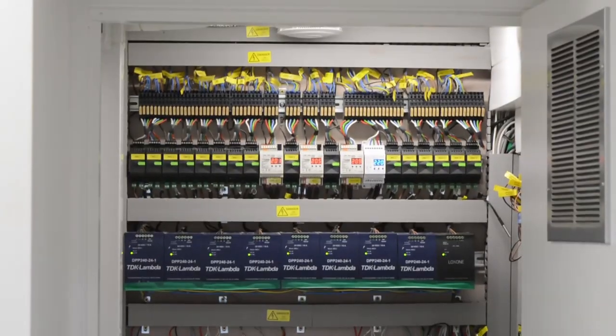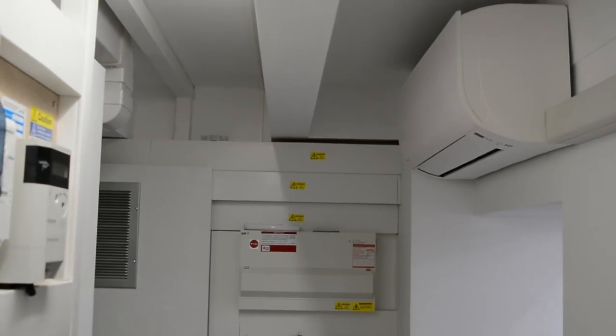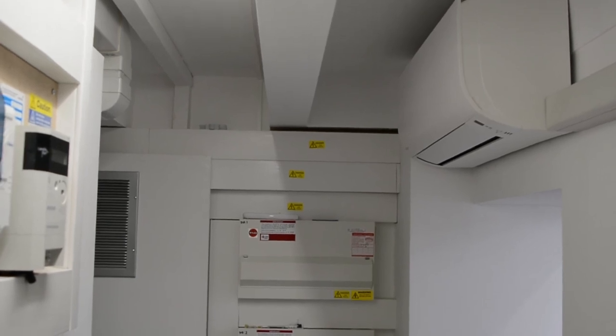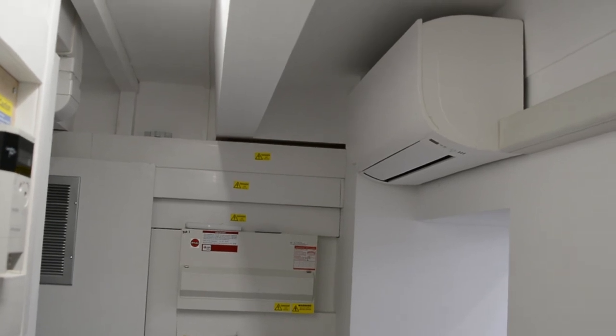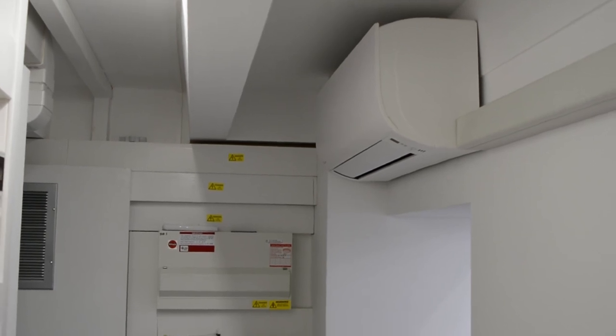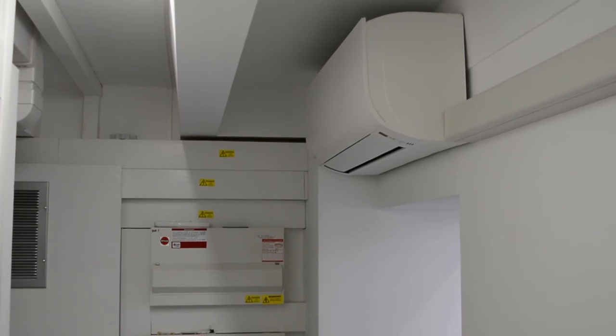Power supply, RGBW dimmers. We need an AC unit in here — those power supplies generate a lot of heat and we need a good AC unit. In the summer it can go over 40 degrees inside here, and the power supplies are rated up to 70 degrees. Even if we install a lot of fans inside, that's not enough.